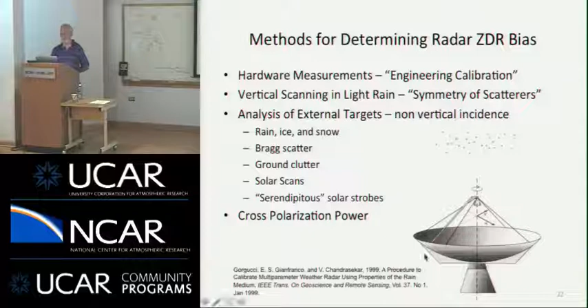So this is a diagram of our system talking about the hardware problem. There are basically three elements to calibration. There's the transmit power bias, there's the receiver channel bias, and there's the antenna bias. These things are actively changing over time. The transmitter power is not always equally balanced. The receiver channel, the difference in gain between the horizontal and vertical, will change as a function of temperature, for example. And so we have to have a way of monitoring this. And so in the NEXRAD, the whole calibration scheme revolves around these waveguide couplers, which allow us to tap out signals from the waveguide to measure the transmitter power, as well as to inject test signals to characterize the receiver.